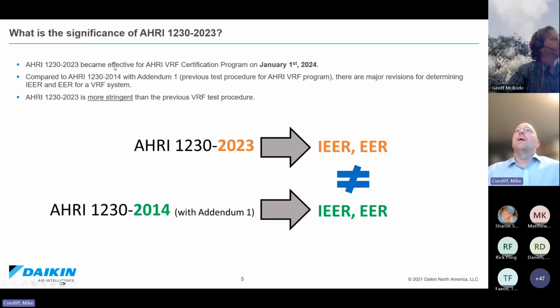AHRI 1230 2023 became effective January 1st of 2024. So the test standard has changed, and with that you're going to see different numbers coming out now versus what you've seen in the past. So the first AHRI 1230 standard was 2014. Roughly 9 years later, here we have 2023 that addresses some of those inconsistencies that Jeff mentioned earlier. AHRI 1230-23 is more stringent than previous VRF test standards.